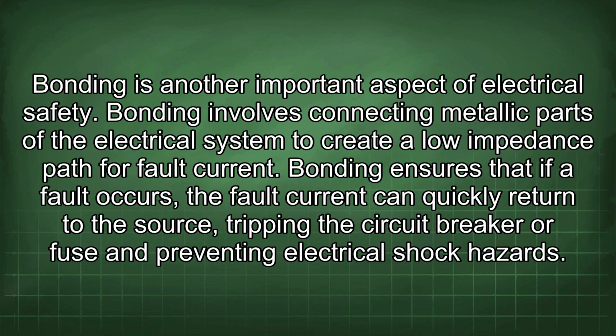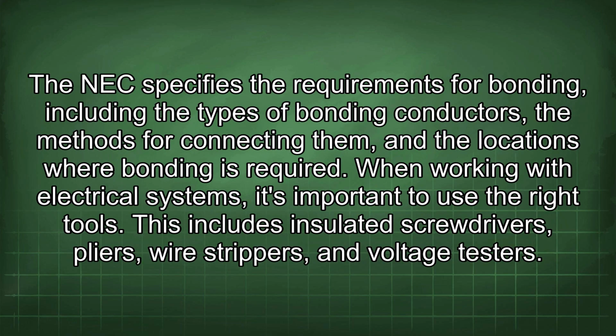Bonding is another important aspect of electrical safety. Bonding involves connecting metallic parts of the electrical system to create a low impedance path for fault current. Bonding ensures that if a fault occurs, the fault current can quickly return to the source, tripping the circuit breaker or fuse and preventing electrical shock hazards. The NEC specifies the requirements for bonding, including the types of bonding conductors, the methods for connecting them, and the locations where bonding is required.